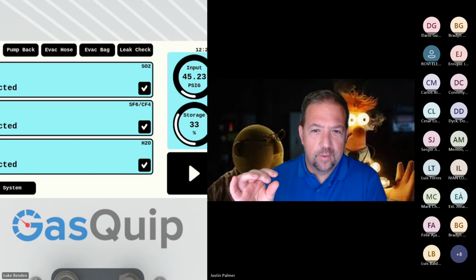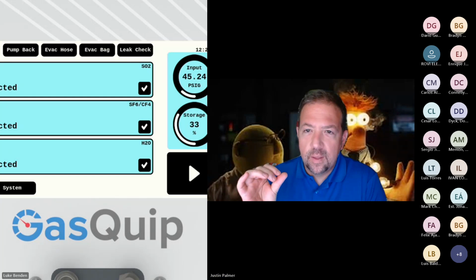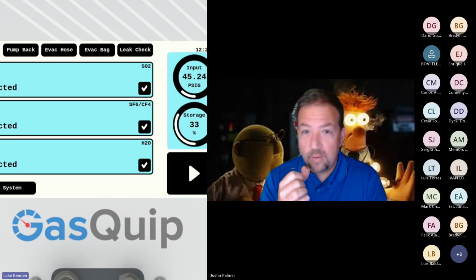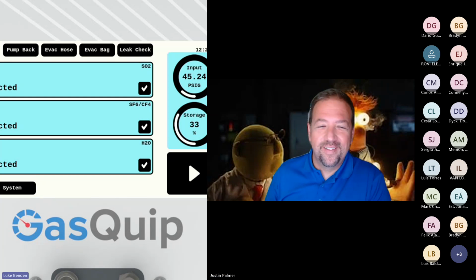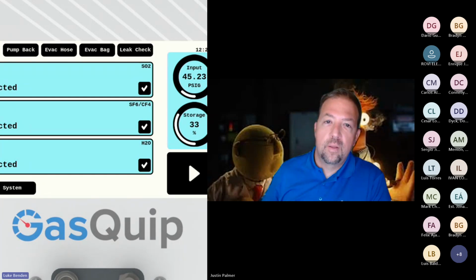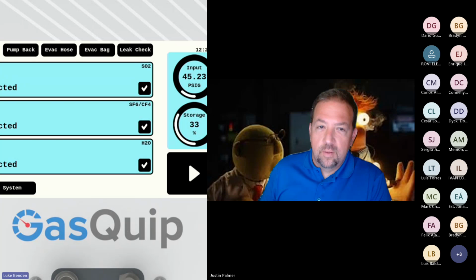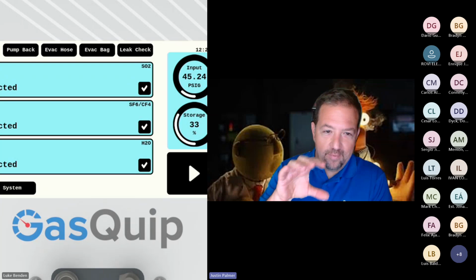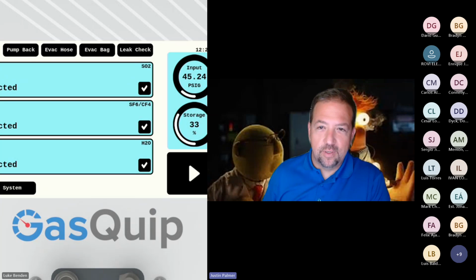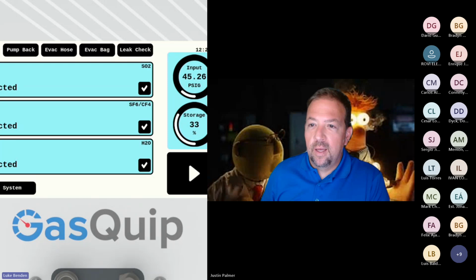Sorry about that. I had myself muted. Yeah, if it sees too much SO2, it'll abort the test, and that's that user set test limit. So if it goes above that, it'll cancel the test because it doesn't want the SO2 running through the system. Awesome. I just wanted to clarify that because that's a good safety feature for people to try to prevent damage to the device. It's something I had noted down to bring up when we had a break here. Great.